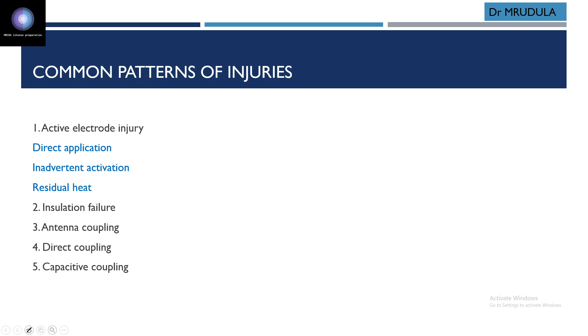So direct application means lateral thermal spread to unintended tissue near the tip of the electrosurgical instrument during activation. Direct application is the most common type of electrosurgical injury. Remember well, this is again a question. The extent of lateral thermal spread depends upon the device used, its power setting, tissue impedance, and the activation time. Monopolar devices have the greatest degree of lateral thermal spread.